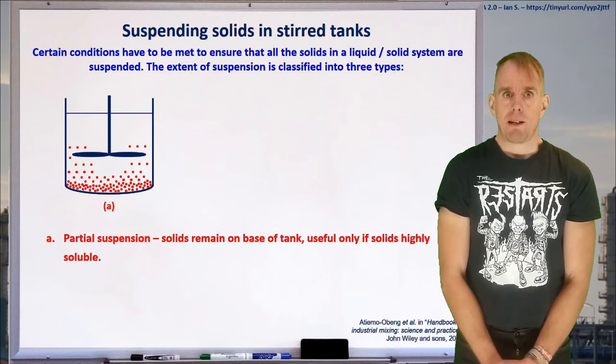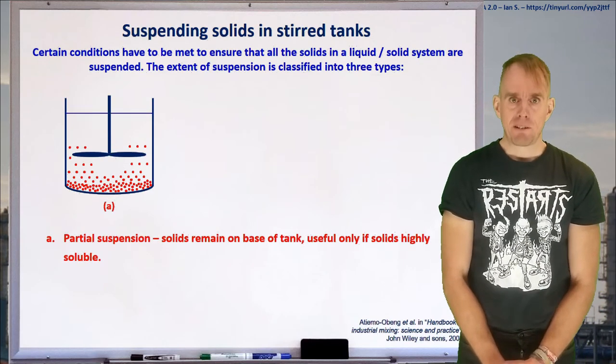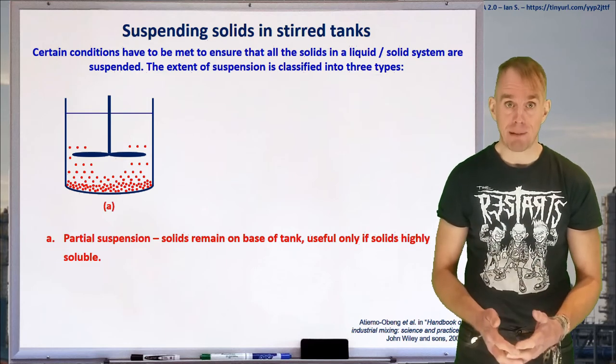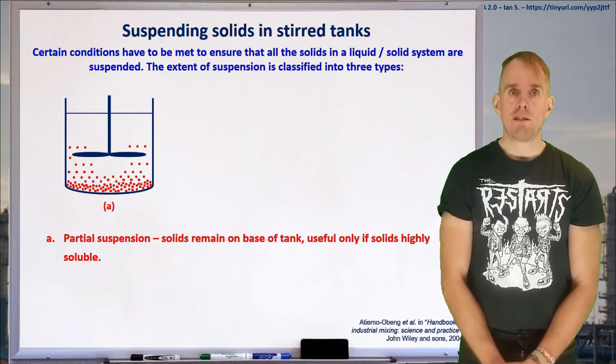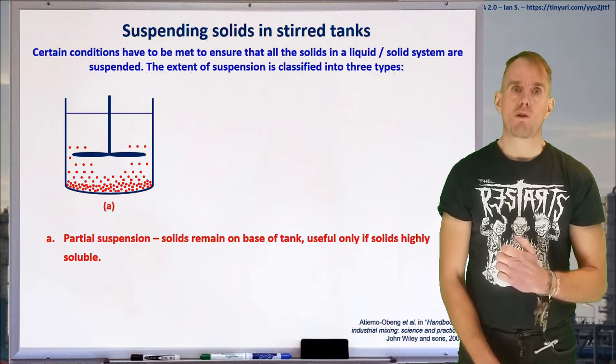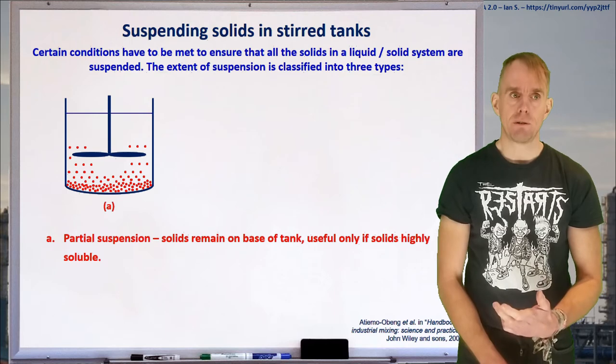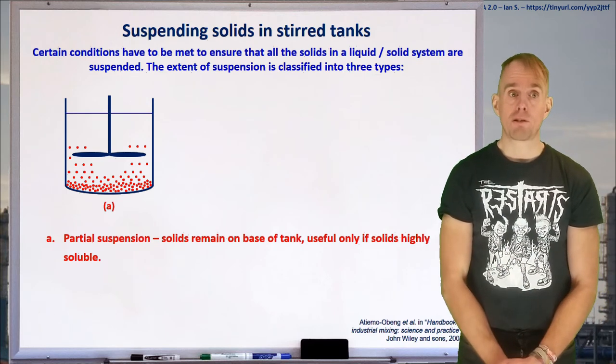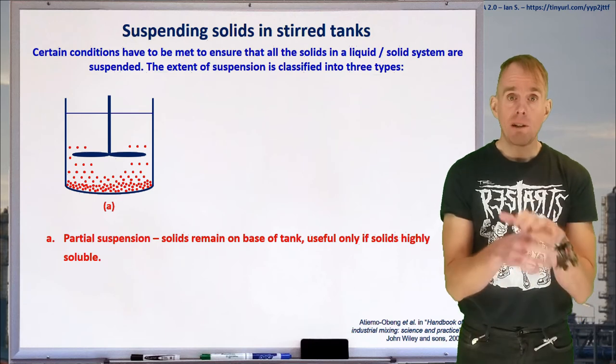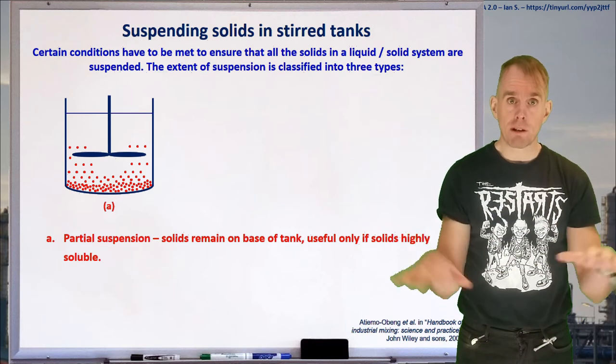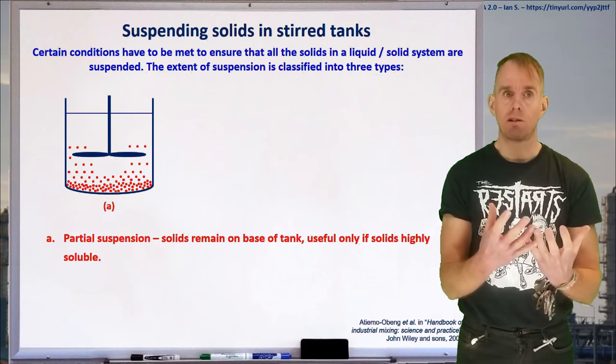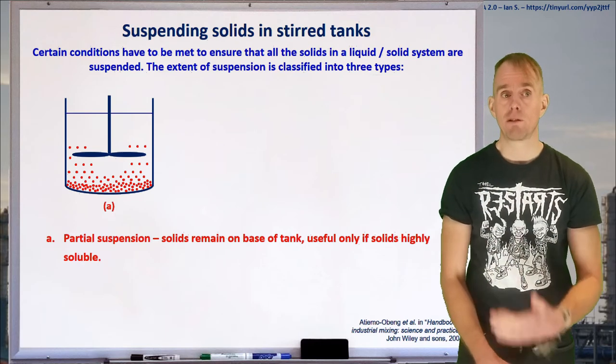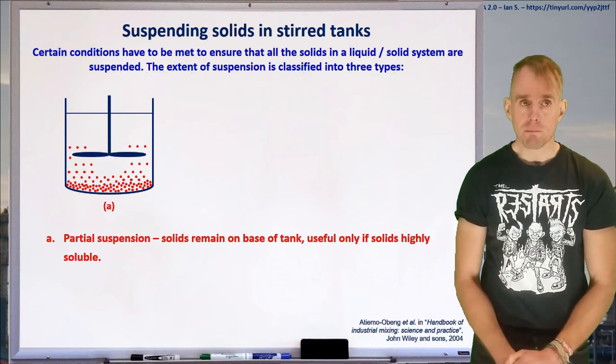Let's think now about keeping particles in suspension. We don't want a beach in our tank. That's bad. And so, what I'd like to do is introduce to you three suspension criteria that you'll commonly find to use. The first that I've put on the board here is called partial suspension. Here is where you have a layer of solids at the base of your tank and some particles in suspension. This typically is something that you don't want to do. It's only useful if the solids are very, very highly soluble.